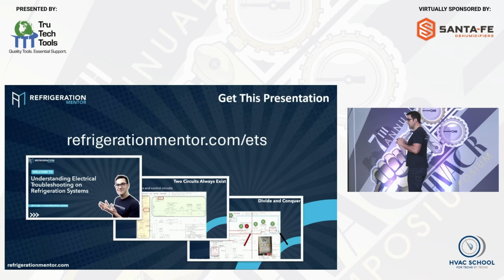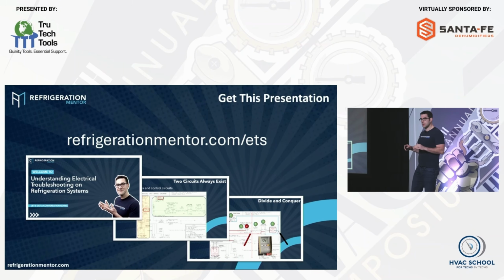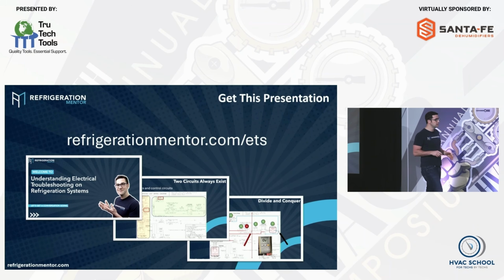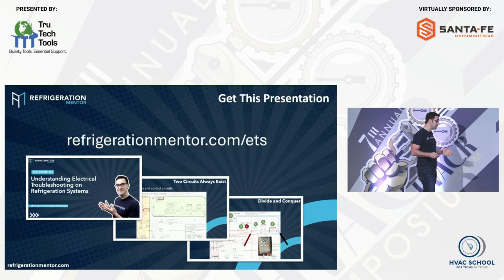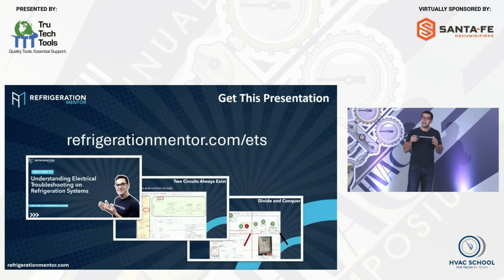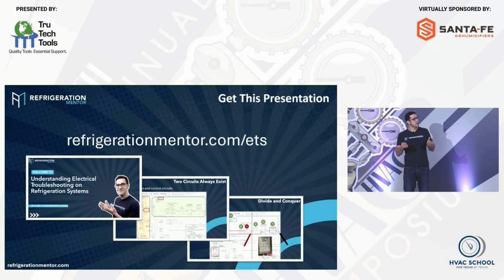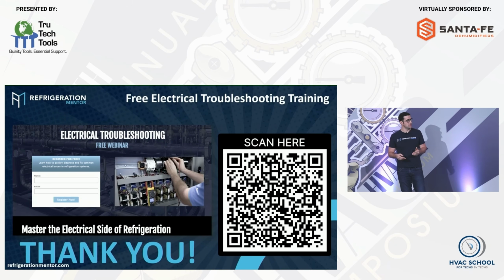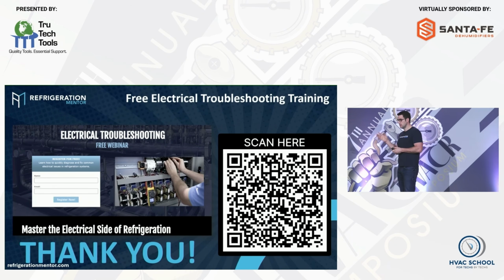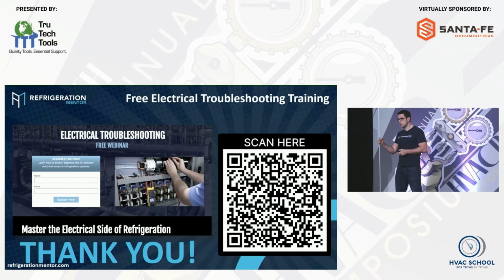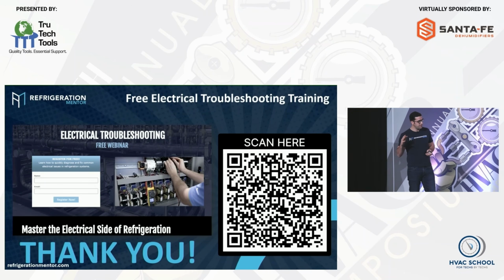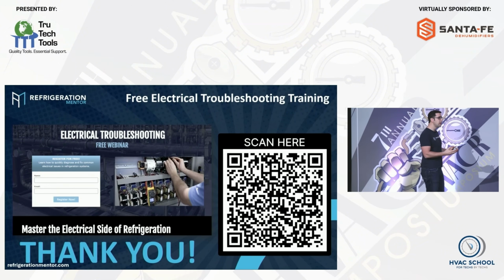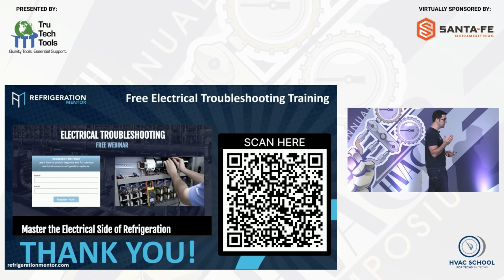One of the biggest things that I've trained a lot of people on electrical, and I've been trained by some of the best around the world on electrical, and I'm just in refrigeration, and I'm continuing to learn more, is that you've got to understand what you're trying to troubleshoot, the logic behind it. We want to understand the whole purpose of what we're doing in refrigeration, okay? The whole purpose is that we need to pull in that contactor so that the compressor starts up, so we can get flow of refrigerant to pull the heat out of the product and reject the heat to the atmosphere.